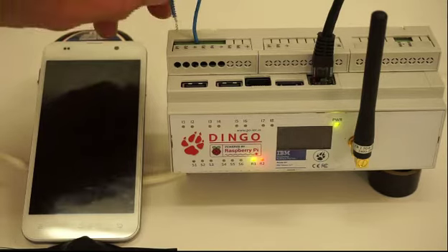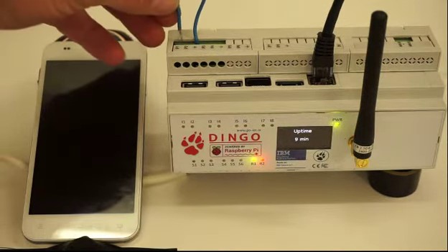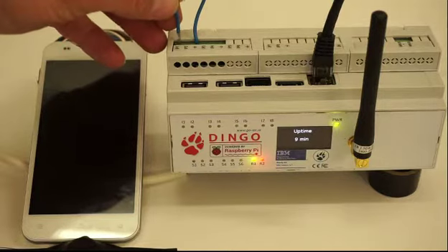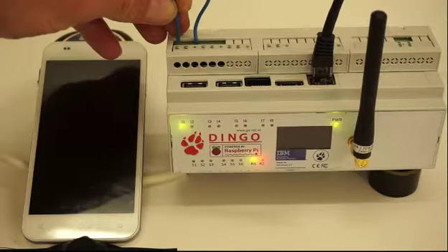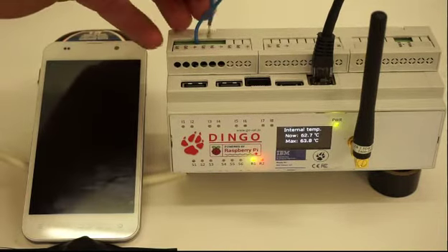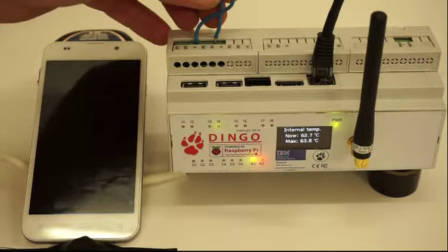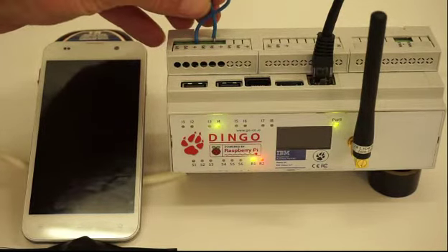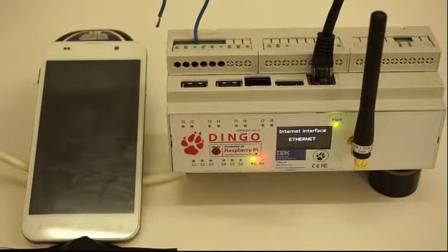So all of those are BACnet objects, as we will see afterwards. So let's try number 1. Yeah, LED 1 is working, number 2 is working, number 3 is working, and number 4 is working. Those are the 4 dry contact inputs, binary inputs. The rest of the binary inputs are wet. We are not going to test those.